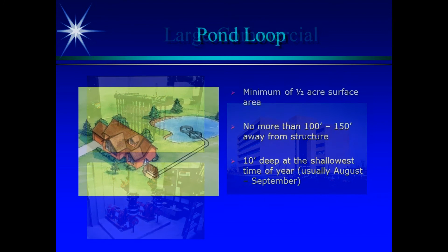The last one is a pond loop. Not everybody's got a pond. You need a minimum of a half acre in surface area, no more than 100 to 150 feet away from the structure. This is a very scientific calculation. Does anybody know why the pond has to be no more than 100 to 150 feet away from the house? If you get out there to 150 feet, we already got what we need. So if the pond's further than that, why would I keep going to get to it?